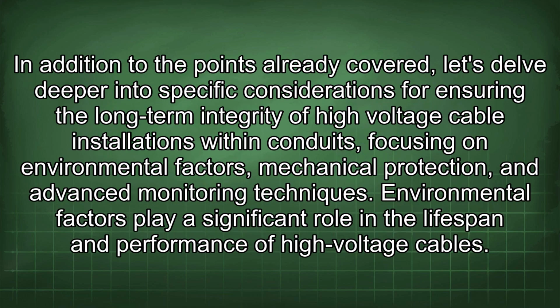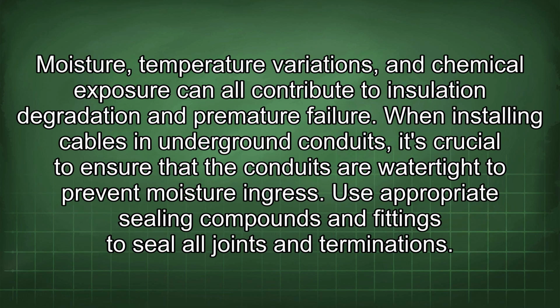In addition to the points already covered, let's delve deeper into specific considerations for ensuring the long-term integrity of high-voltage cable installations within conduits, focusing on environmental factors, mechanical protection, and advanced monitoring techniques. Environmental factors play a significant role in the lifespan and performance of high-voltage cables. Moisture, temperature variations, and chemical exposure can all contribute to insulation degradation and premature failure.